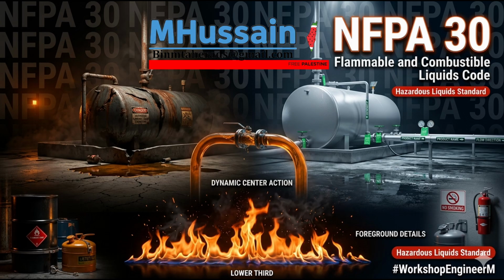So, a non-relieving container is exactly what it sounds like. A rigid, hermetically sealed vessel, like your standard, heavy-duty 55-gallon steel drum. And a relieving container is designed to lose its structural integrity under heat. Like a large plastic intermediate bulk container, an IBC that just melts. Exactly.